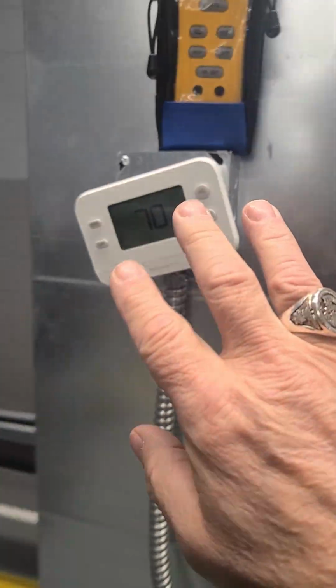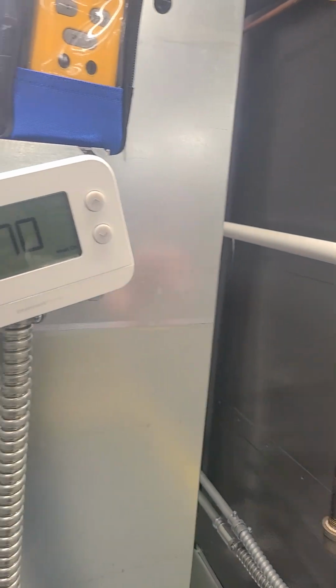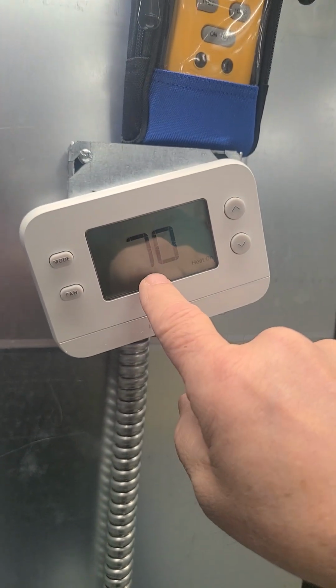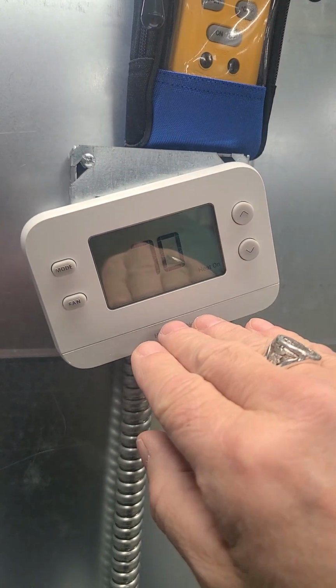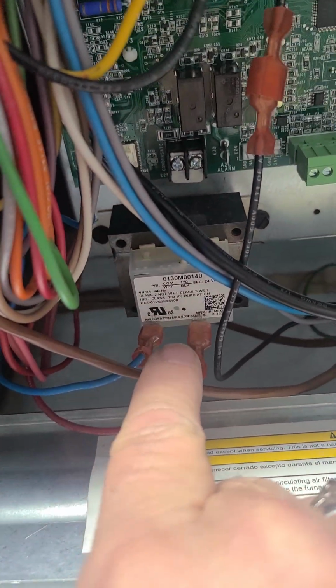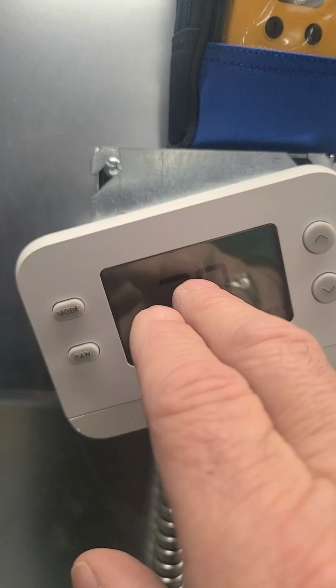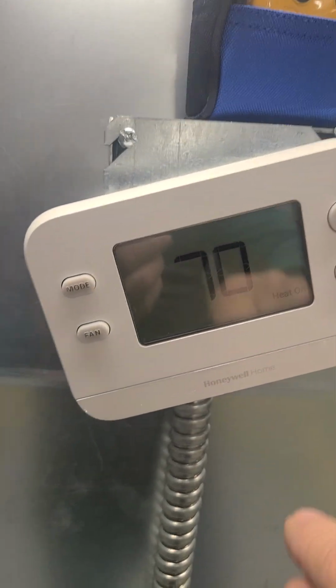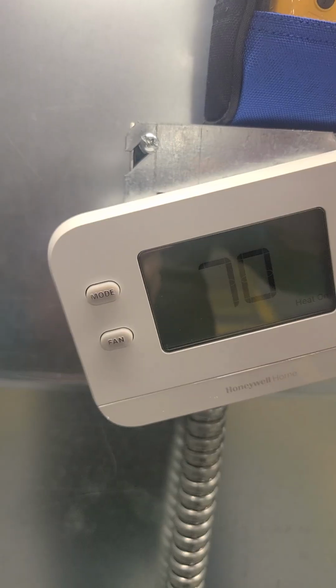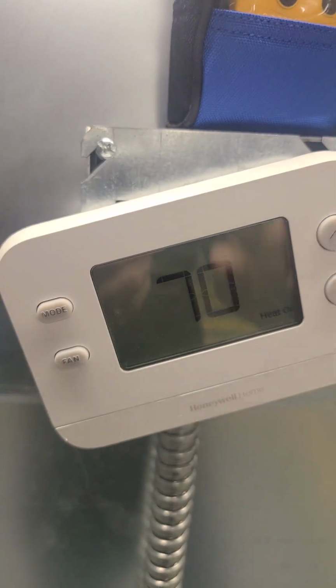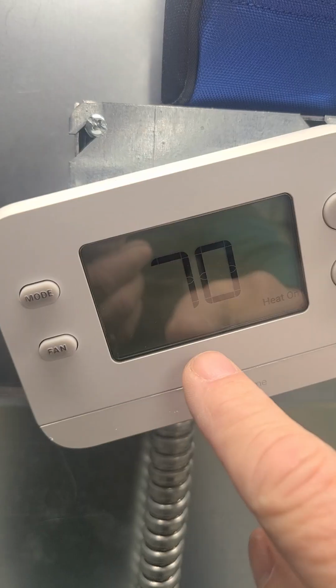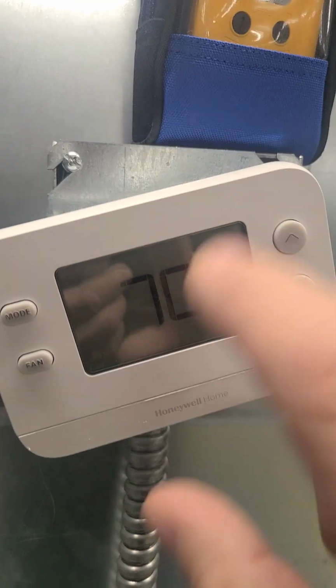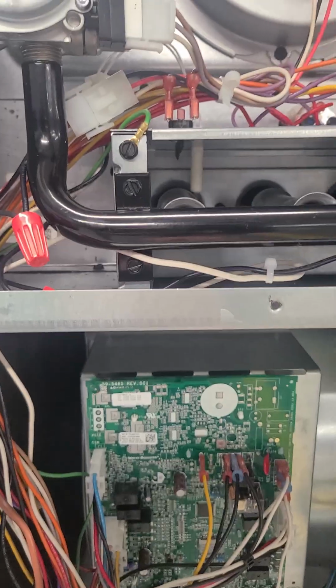Now, to get the furnace going, once the set point of the thermostat is above the actual sensed temperature in the conditioned space, then the 120 volts will go down to this 24 volt transformer through the system board. It will supply the 24 volts to the R terminal of the thermostat, and then once that set point is above the measured conditioned space temperature, the contacts for the W terminal of the thermostat will close, and then that signal will come back down to the system board.